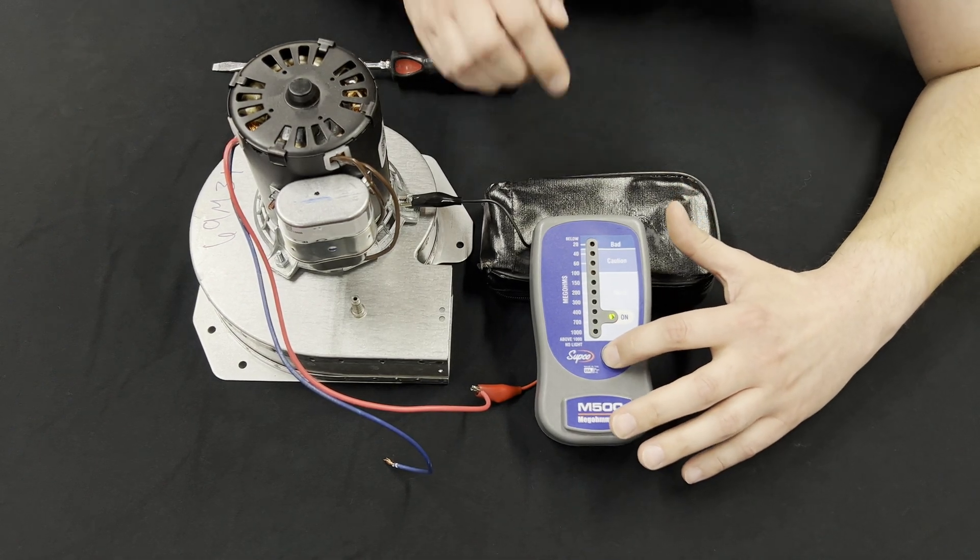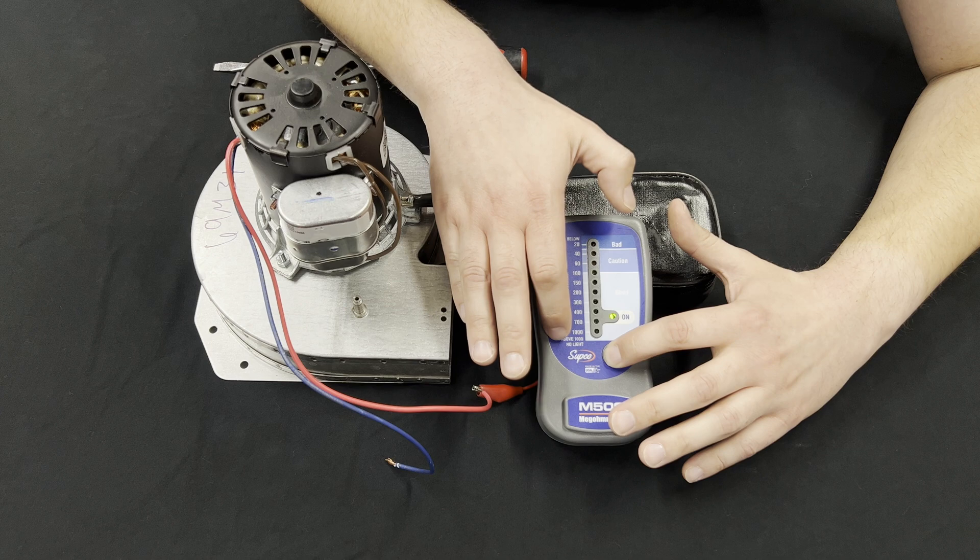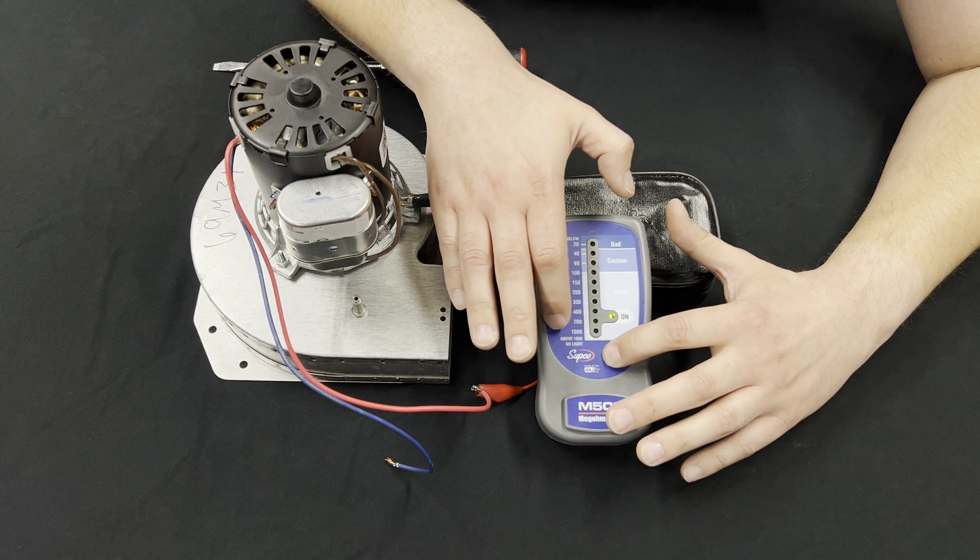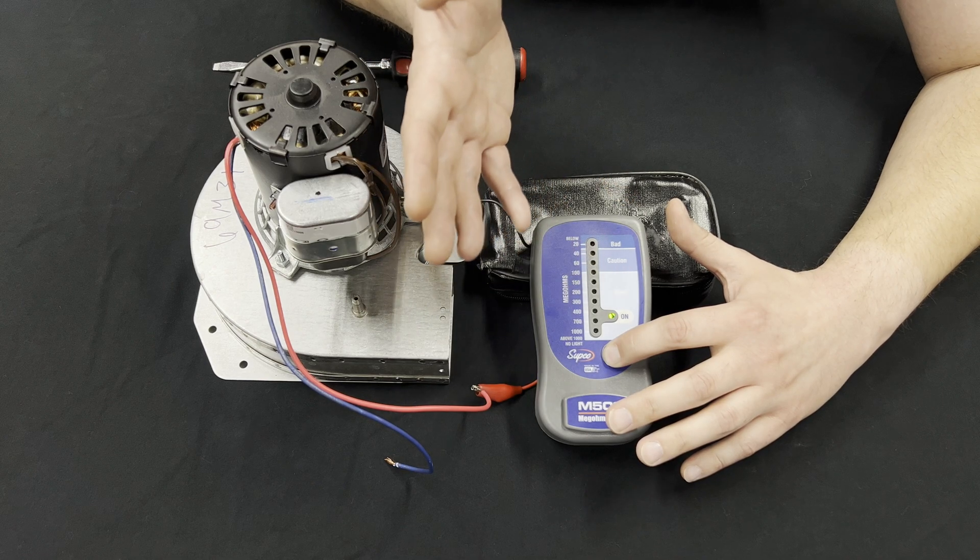By pressing the button on this, we'll see three quick green lights go from 400 up to a thousand. This indicates that the insulation is above a thousand mega ohms and is in great shape.